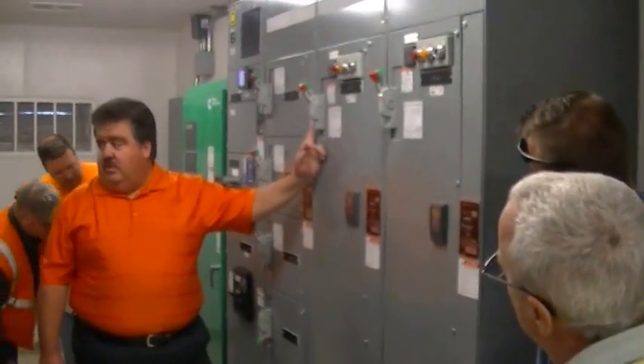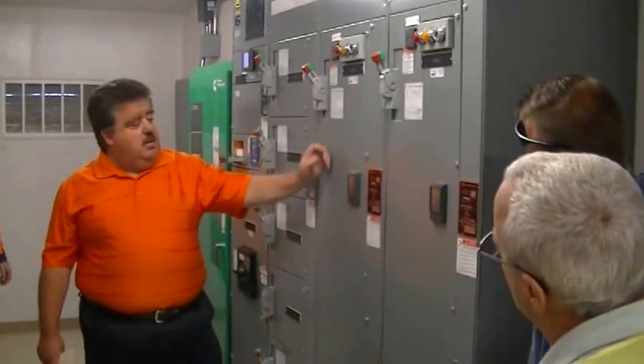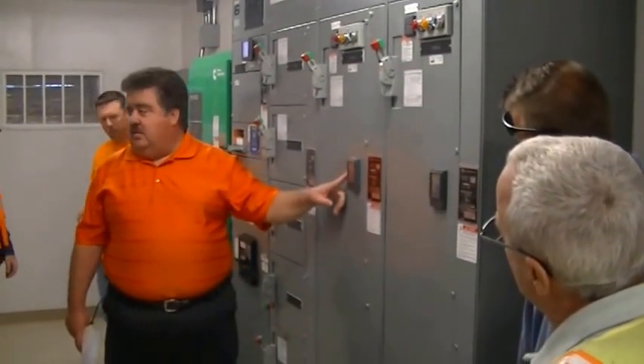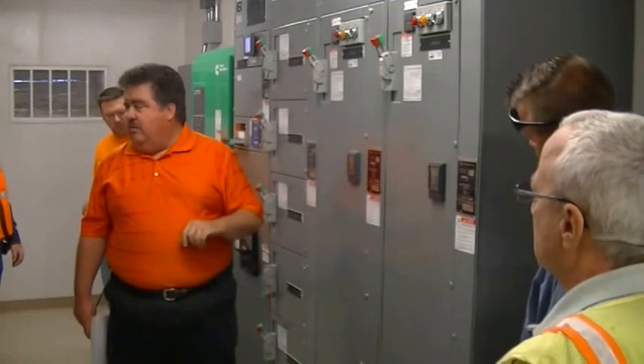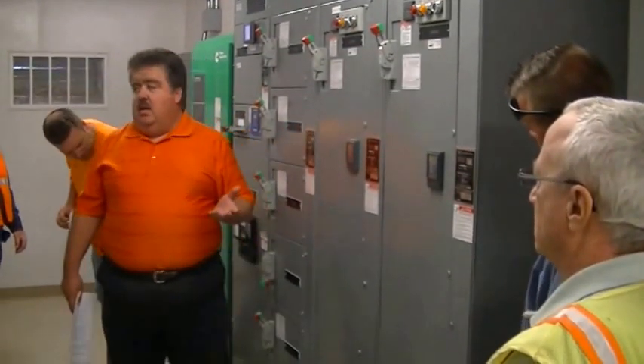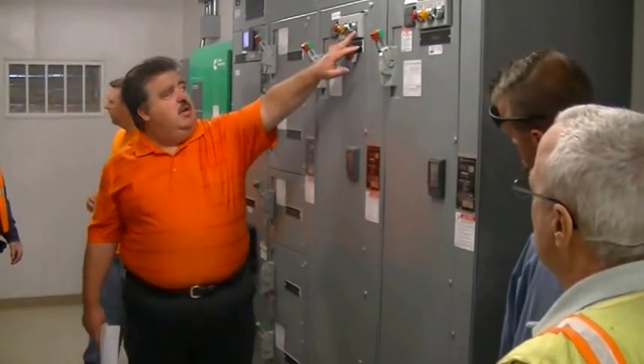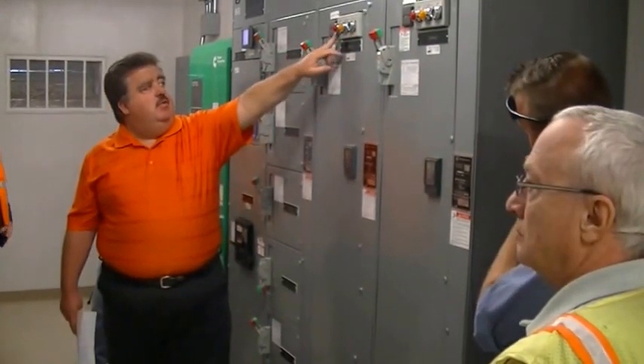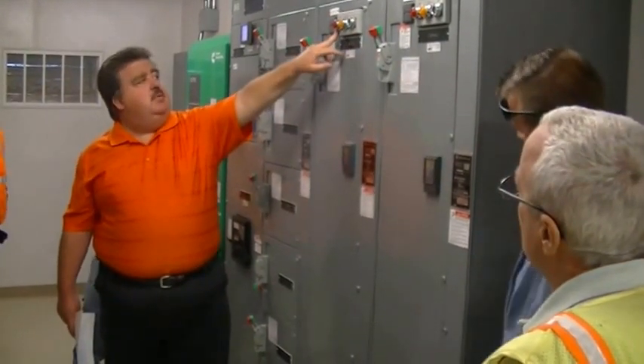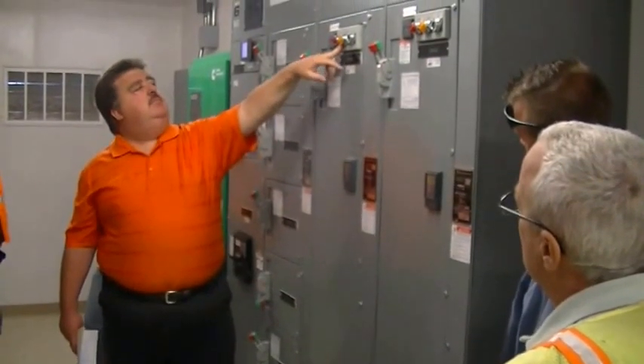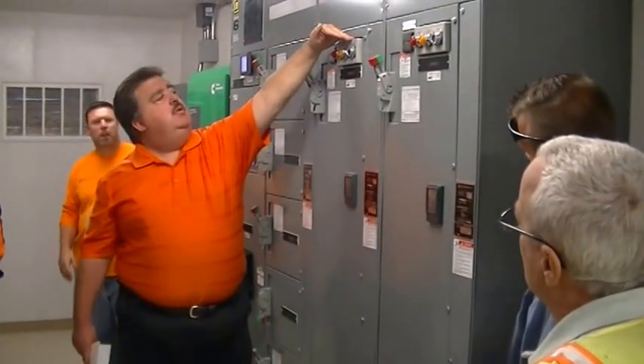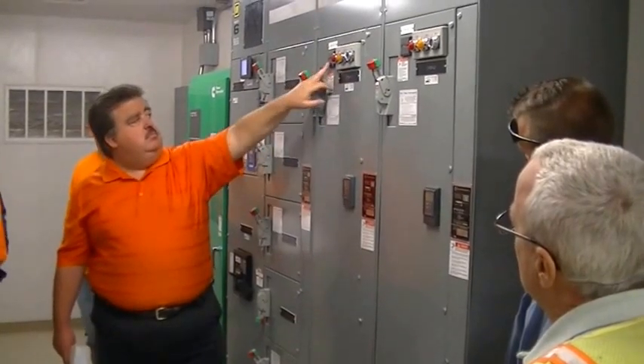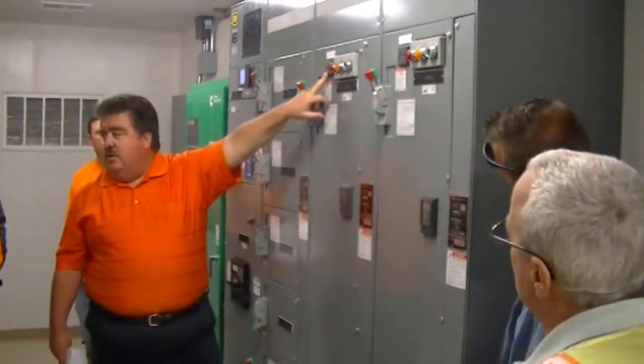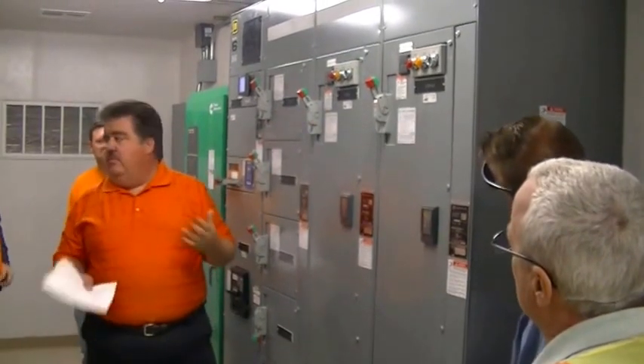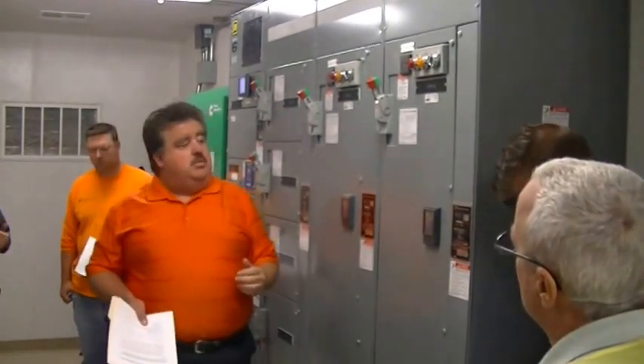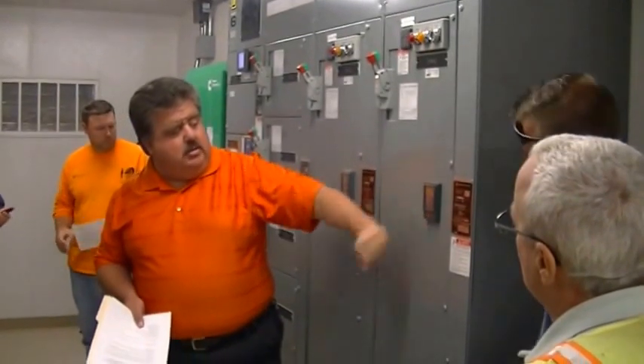So you've got your disconnect and your lockout tagout mechanism. This will tell you what the status of the soft start is. So this one's ready for run. It's waiting for a run contact. If it's faulty, you have to reset. It'll tell you if the pump's running. And this is your pressure switch low. How many hours, so you look at balance for your cycle on your pumps. Same thing here, status on this one.